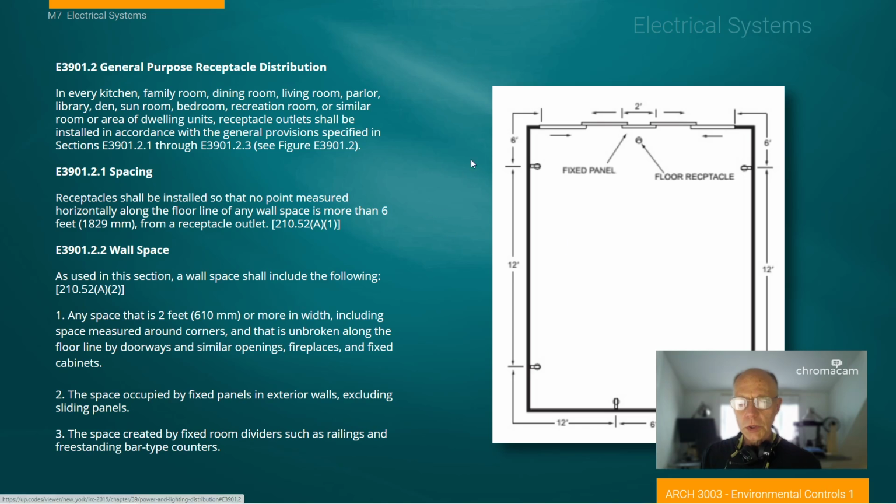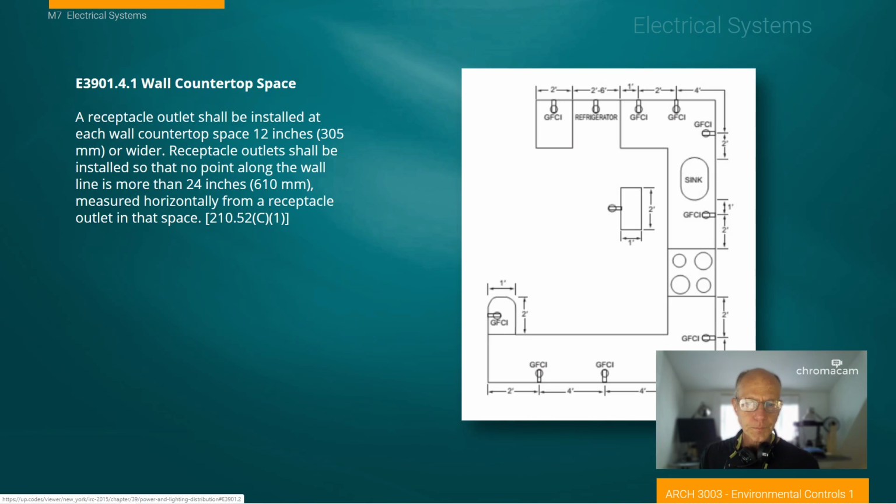One of the mistakes that's easy to make is to take that idea of the 6 foot distance for a power cord and think that that's the requirement of spacing. But the requirement is that the appliance be no more than 6 feet away. So you can go 6 feet either way, which comes to 12-foot spacing. I'm not saying that that's always going to be what the code is. That's typically what the code is currently. And when we get to kitchen, the spacing changes.